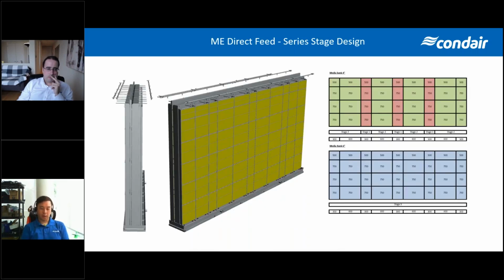This is another interesting one here in terms of a series design. So this client was more concerned about air stratification within the airstream on a fairly large unit. So what we've done here is actually just put 2 banks of media, 1 downstream of the other. So in this case, we have a 4-inch bank upstream. Directly downstream from that, on the same frame, same module, we have a 6-inch bank of media. And the way that this unit was controlled initially was stage 1 was the 4-inch bank on by itself. Stage 2 was the 6-inch bank on by itself.